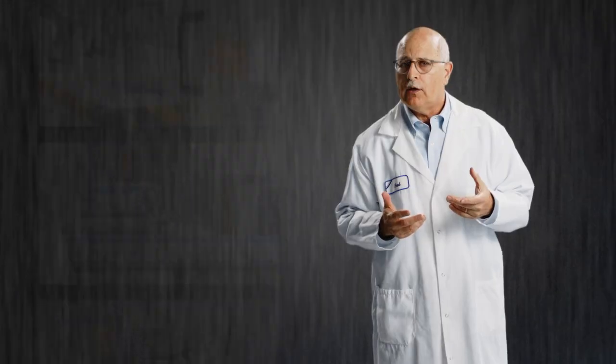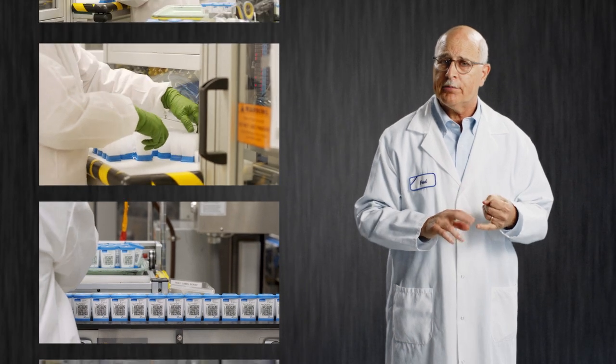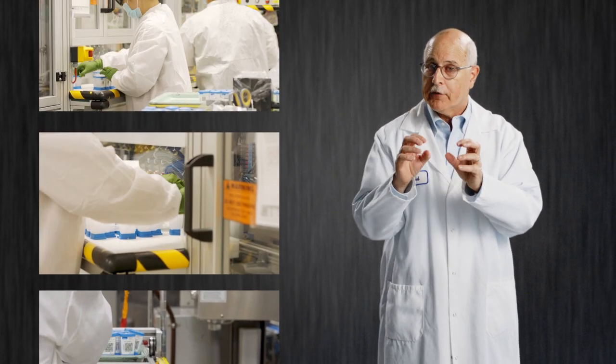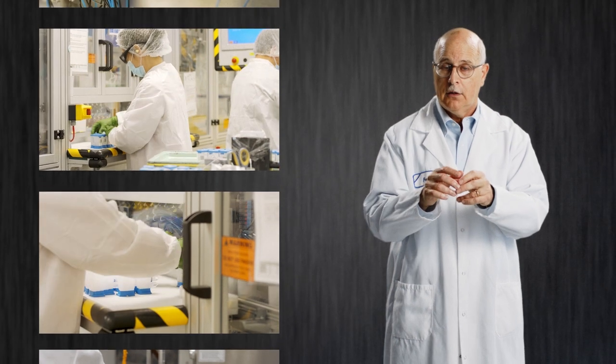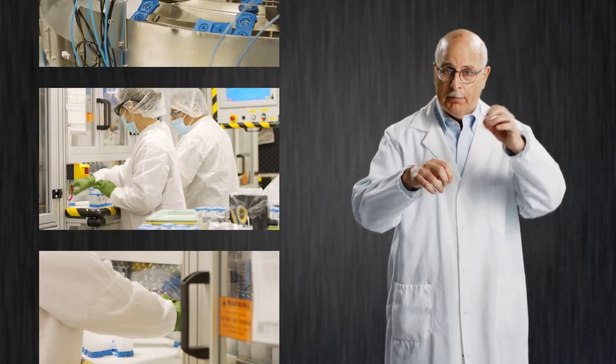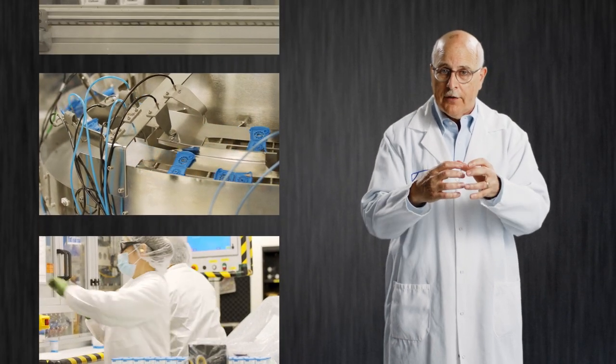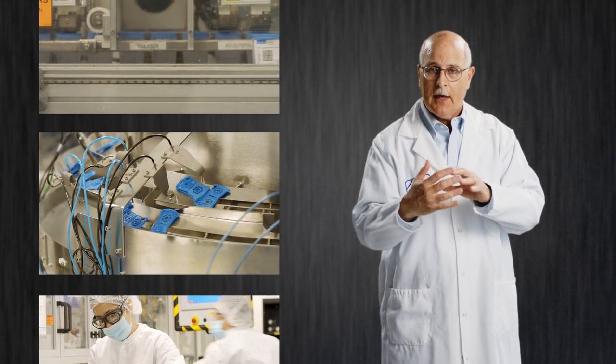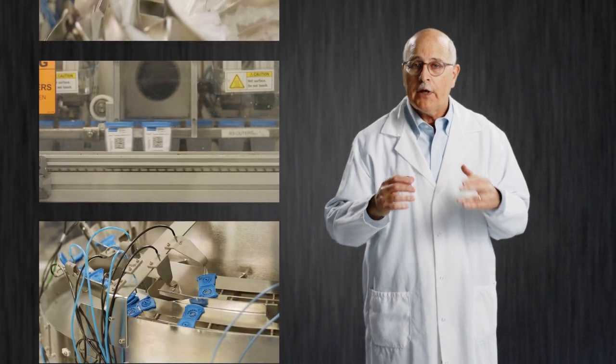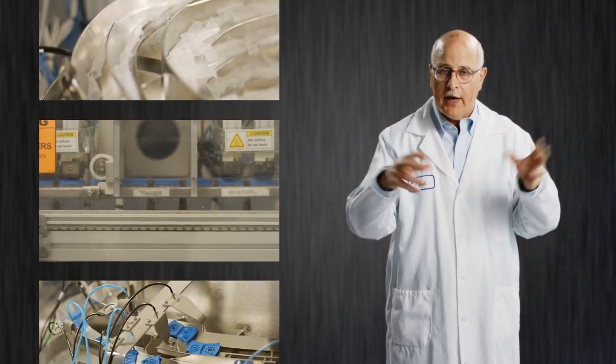So now we have the situation where the research and development team has done their job. They've developed this assay. Now we have to hand it off to manufacturing and say, build this for us. So what does that actually mean? Well, this is a pretty complicated process because we have a cartridge, a very intricate piece of plastic. We have reagents and buffers and beads that need to go into that. We need to put this all together and have a label on it. And in order to do that, we need a pretty competent team of people to put everything together.